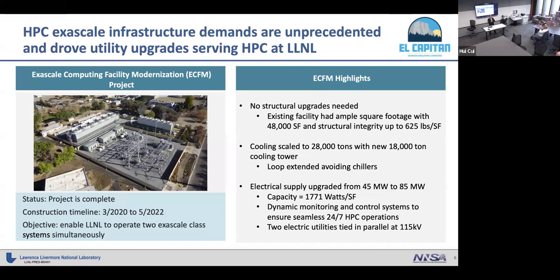But when we deploy a system, we also keep the previous system up and running, and we wanted our facility to be able to handle two exascale systems at a time. So we want to deploy the system after El Capitan while El Capitan is still running. That means if we want to handle a 30 to 40 megawatt system, we need over 60 megawatts that we can deliver to the floor.